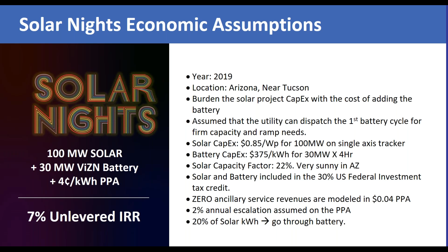It's important when you look at the impact of dropping a 30 megawatt battery for one cycle on a 100 megawatt solar system: that 30 megawatt battery can hold about 120,000 kilowatt hours if it's a 4-hour battery, which is about 20% of the plant's output. So 80% of the plant flows directly to the grid daily. Whether it's the lithium system or the ViZn system, it gets charged by the solar, and it only takes about 20% of the overall plant output to charge it for one cycle.